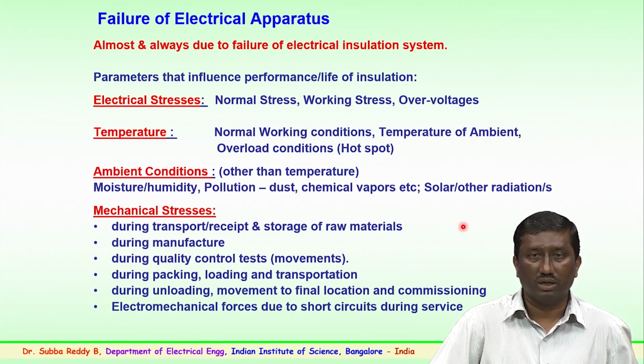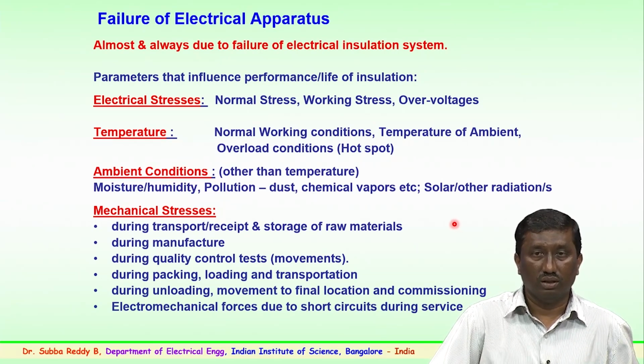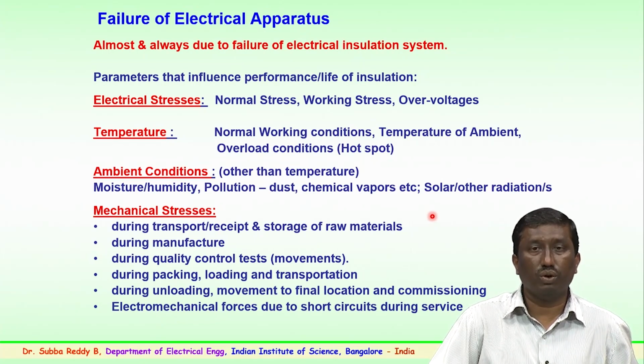The second is the temperature. Again, the insulation has to withstand, along with the electrical stress, the normal working conditions. There is also the temperature due to overload conditions, particularly in transformers, where hot spots develop in the multi insulation like the oil and the paper, along with the electrical stress. In such cases, because of overload conditions, the temperature surrounding the insulation will be higher. So, here again the temperature plays a role in the life of an insulating material or an insulation system.